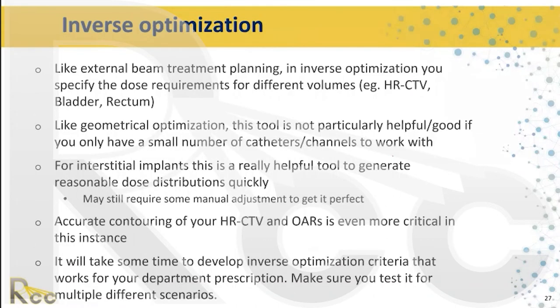Inverse optimization is the latest tool available, similar to IMRT inverse planning — you specify dose requirements for different volumes such as HR-CTV, bladder, or rectum, and the system calculates dwell positions. Like geometric optimization, it is not particularly helpful with a small number of catheters, but can be useful for interstitial implants to generate reasonable dose distributions quickly. However, this must be verified in a manner consistent with the institution's expectations.